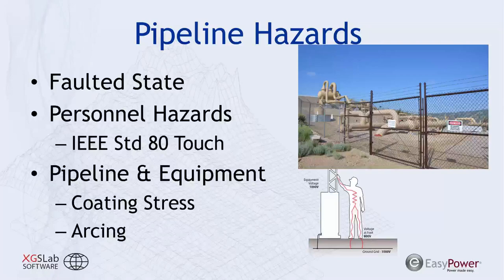Other sorts of hazards that we could see are a coating stress. This is if you have enough voltage between the pipe wall and the soil, you could have a sufficient voltage to exceed the dielectric strength of that pipeline's coating. And that could create more of that AC corrosion farther down the line, or you could even see the possibility of arcing from the transmission line to the pipeline, causing immediate damage of the pipe.